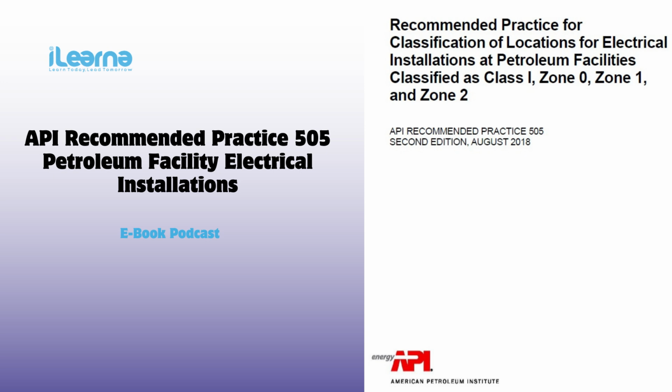Makes sense. So what about Zone 1? Is that a little less risky? Exactly. Zone 1 is where a flammable atmosphere is likely to occur under normal operating conditions. But it's not always present like in Zone 0. Think of areas around pumps and valves, or maybe flanges, places where leaks might happen occasionally. So it's still risky, but not like a constant state of emergency. Right. You still need to be careful and use the right equipment, but it doesn't have to be as extreme as Zone 0. Got it.